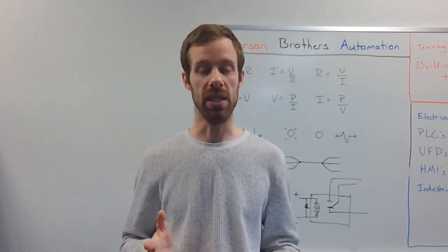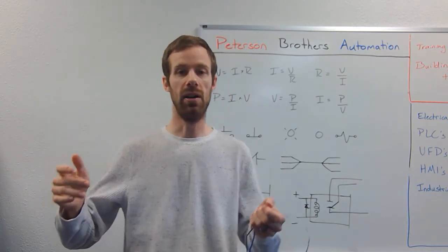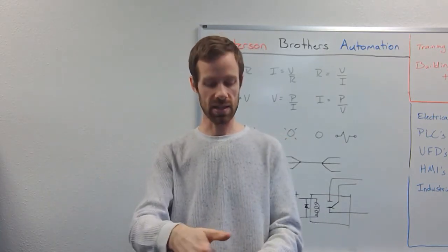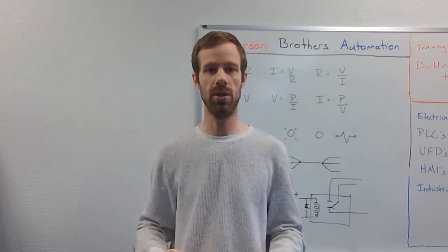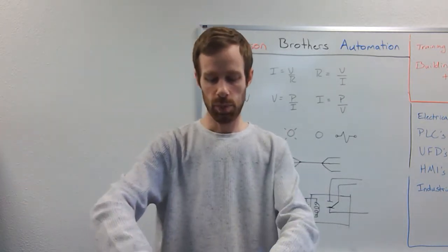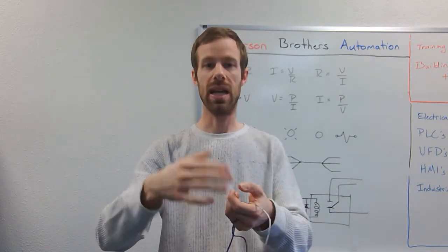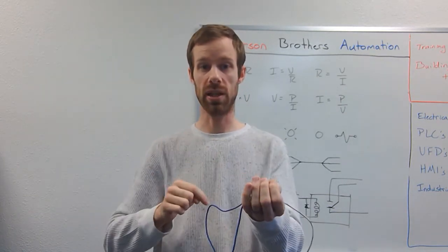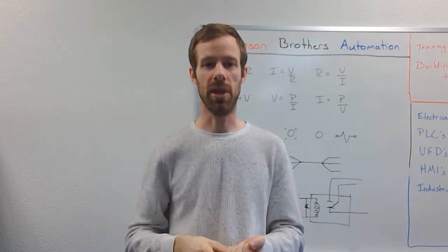If I had done that from the beginning, this is simply a matter of, while the machine is still running, I don't have to disconnect anything, I don't have to take apart screw terminals. I simply go make my right length of wire, attach it into my device, put it into the appropriate terminal block next to the terminal blocks where these are connected, and then stick my jumper in place.